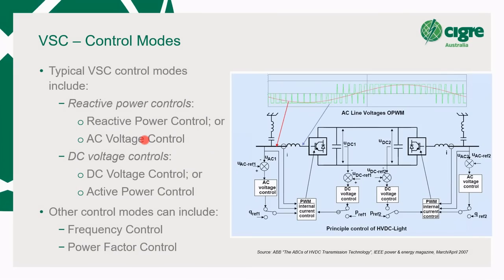Now, because of what I mentioned about being able to independently control the reactive power, each converter can have its own reactive power control. Actually, I'll go as far as to say each converter must have a reactive power control and a DC voltage control. So the reactive power control is pretty much the choice. The typical choice is reactive power control, RPC, where you type in a megavar value, positive or negative, and the converter will do it for you. Or you could put in an AC voltage and have the converter measure the AC voltage and then adjust the reactive power to try and maintain that AC voltage set point.